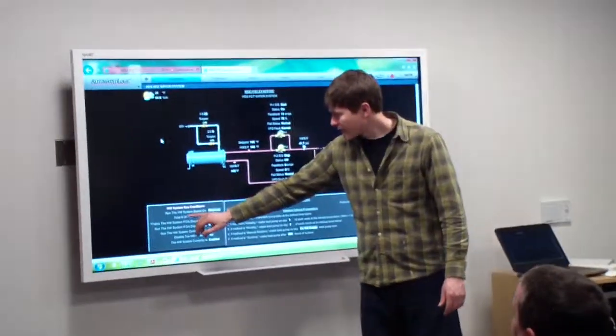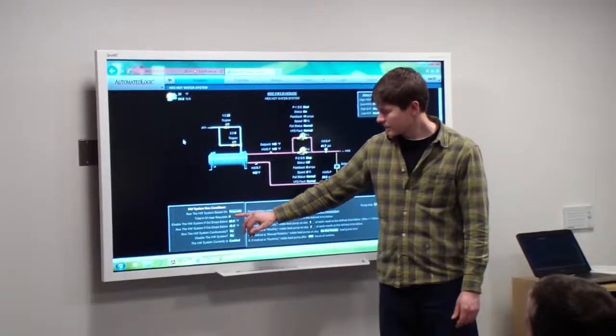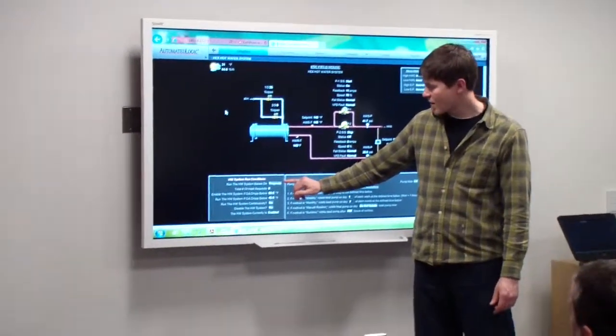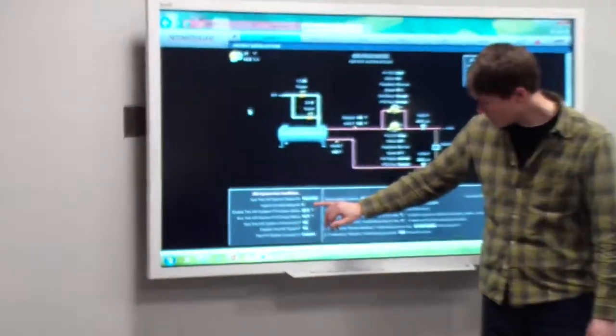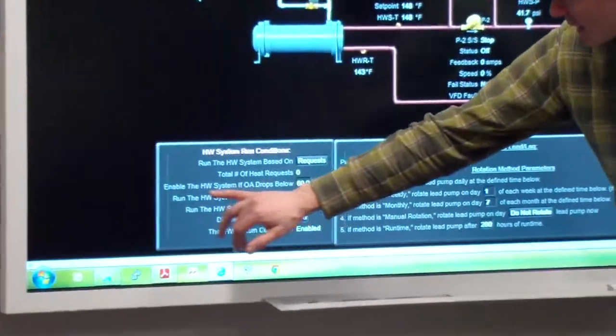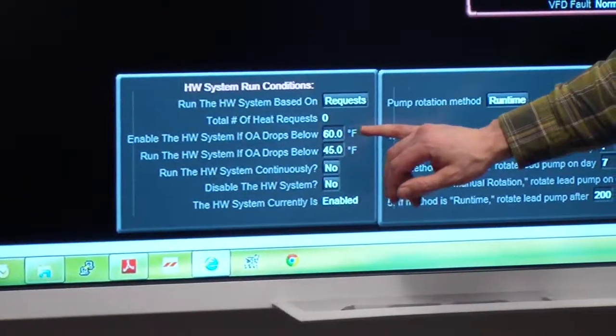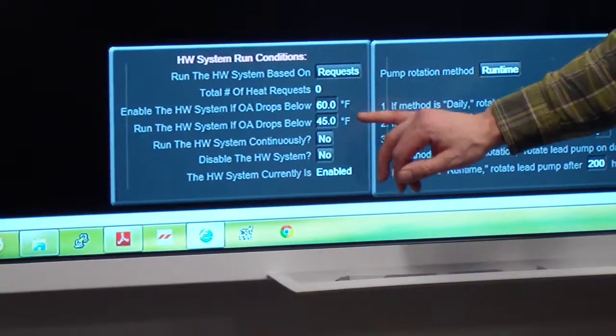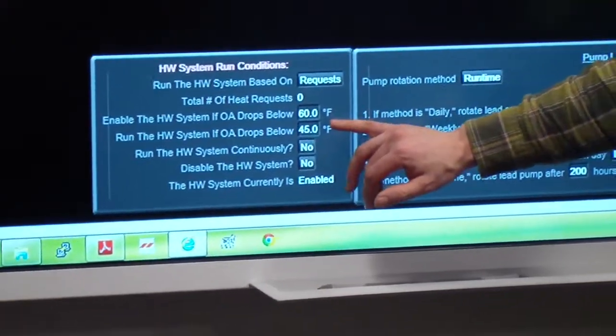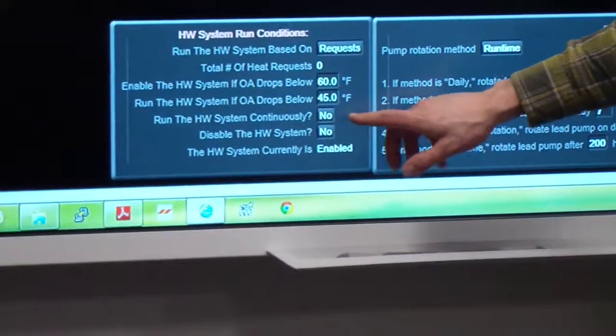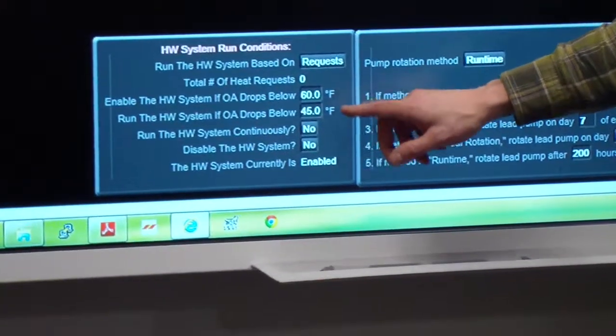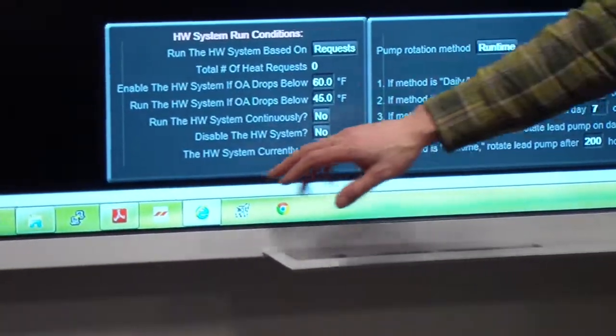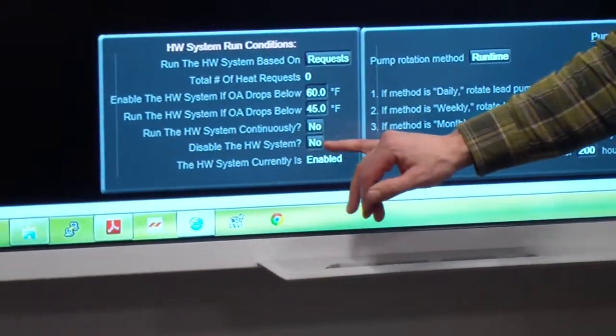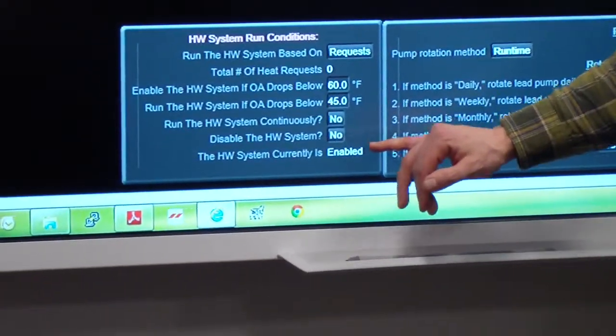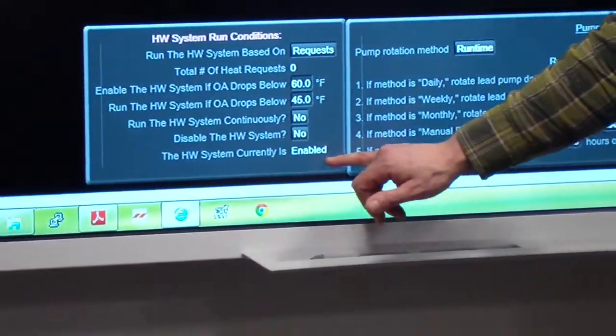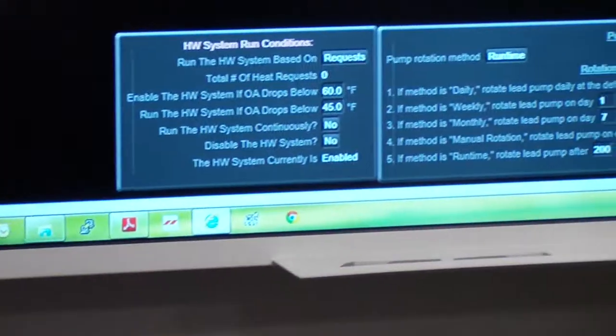Schedule. So now you have your run conditions. It shows that the system's run based on requests. You've got no requests at the moment, but it also comes on if your outside air temp is below 60 degrees, and below 45 degrees it will run the hot water system continuously. If you feel that some of these functions aren't working, you can play with that button, or you can disable the hot water system if you are working on it and you don't want it to run. And then this tells you what state it's currently in.